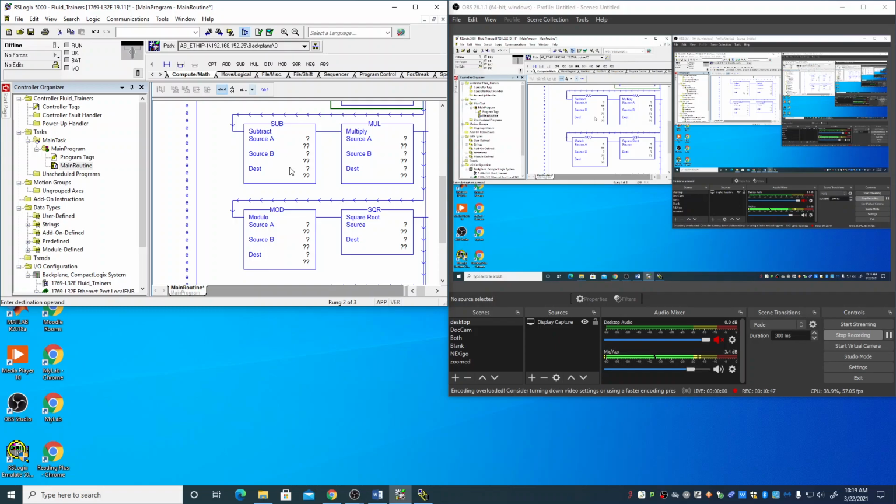It jumps that 300 numbers at a time, and you're like, why did it jump so much? Well, it's because of the analog digital converters built in these PLCs. They don't have a high enough resolution to see a finer degree of motion. Right? So we don't have that option. So just because we convert something to a real doesn't mean we're going to magically get more information out of it. It just means that we now can have a decimal place when you're doing like math equations and like that. It may be helpful to you.